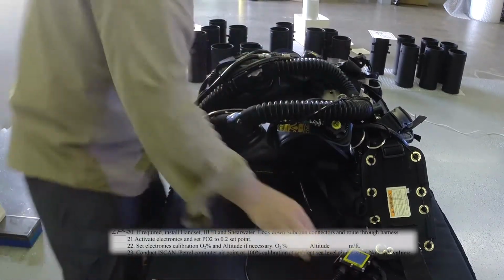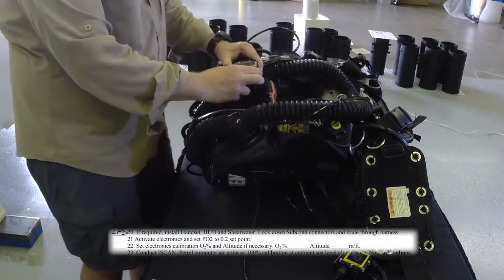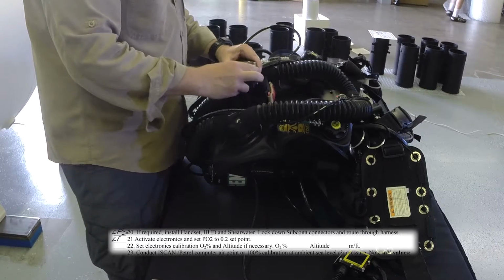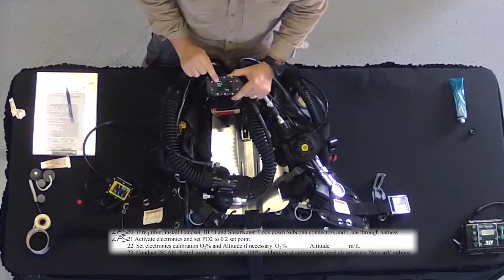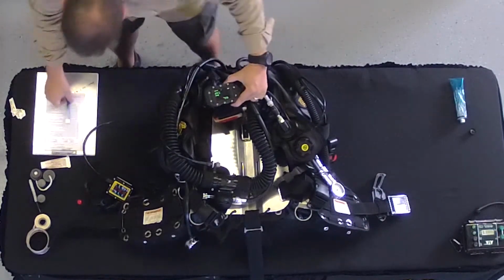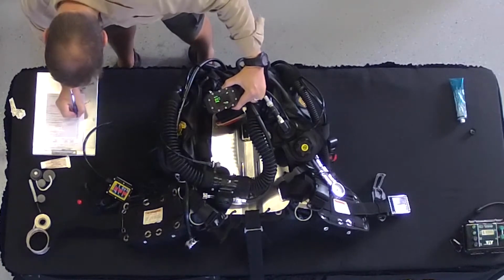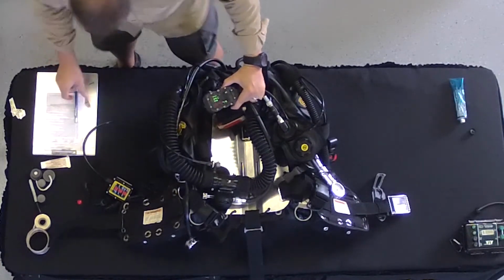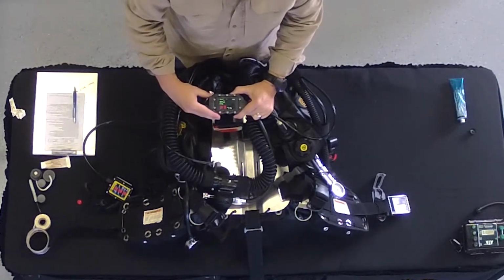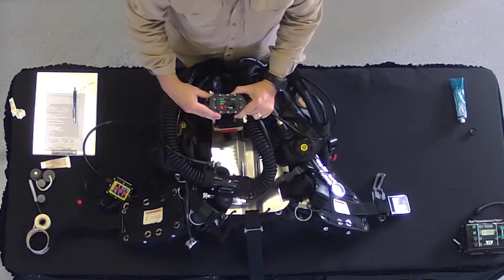Now I'm activating all the electronics. Step 21, activate electronics and set PO2 to 0.2 set point. 0.2 is roughly ambient air at sea level, and that's to ensure that the solenoid isn't clicking away, burning the battery up.